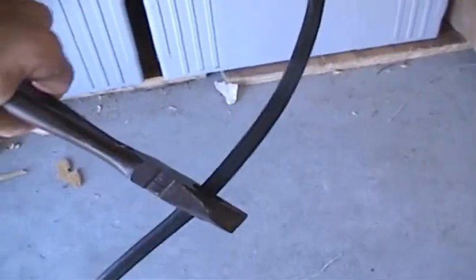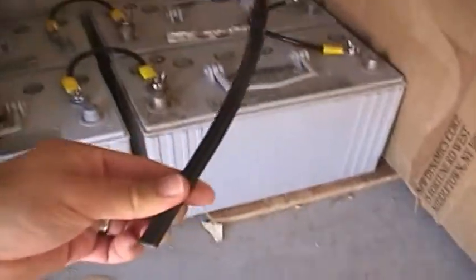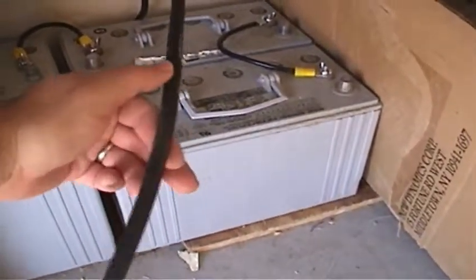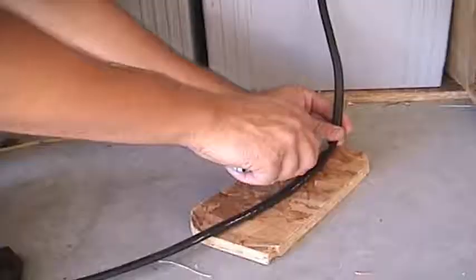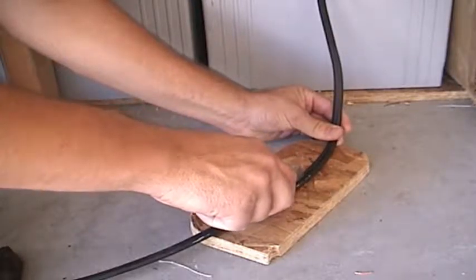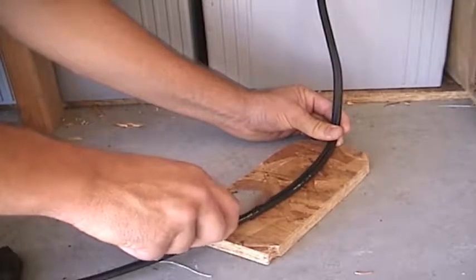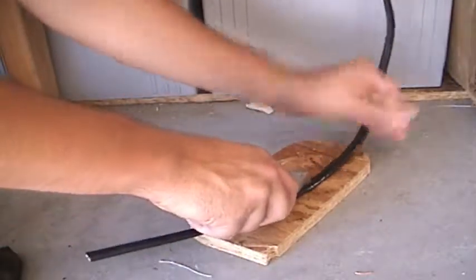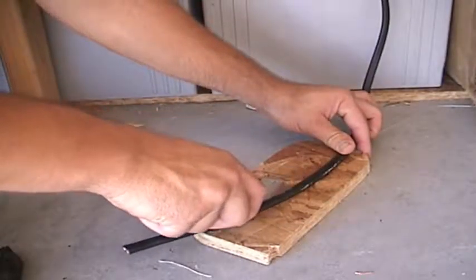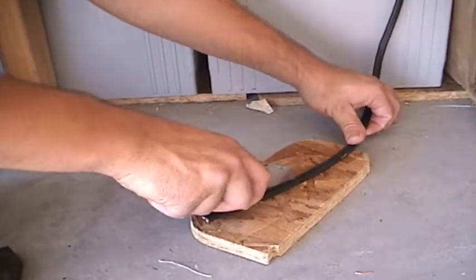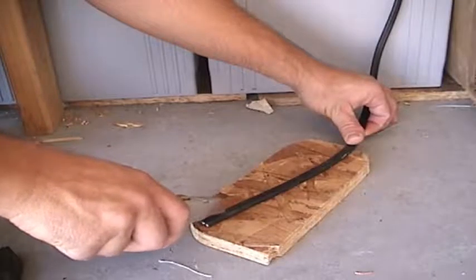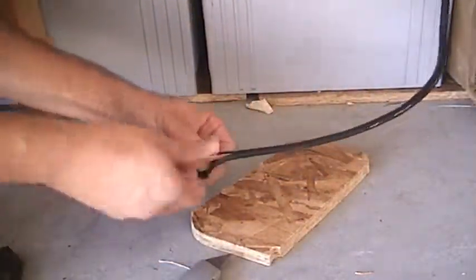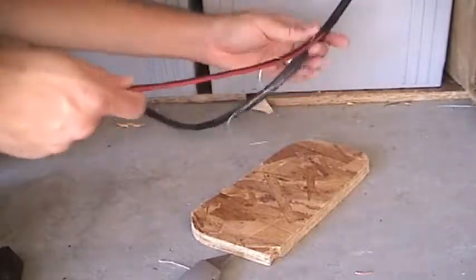Now that we've run our 10 gauge outdoor cable from the second circuit breaker down to the battery bank, we're going to measure about 1.5 feet beyond the battery bank and cut off the excess cable. Go ahead and discard the extra piece, and now we're going to remove about 1.5 feet of the outer skin from this end of the 10 gauge outdoor cable. Using your utility knife, cut through again about 1.5 feet of the outer skin. Be careful not to cut through to the 2 conductors below. Okay, peel the skin back.